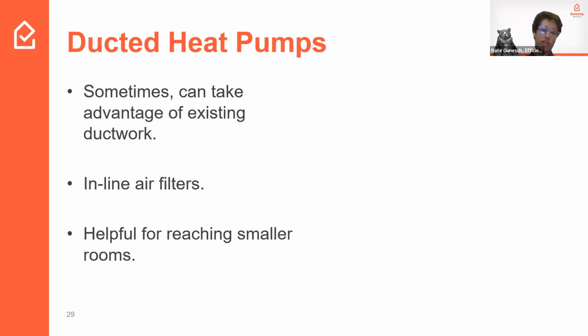The distribution temperature is kind of the key element for whether or not your existing ductwork will work. Sometimes because we've relied on the high heat from furnaces, people have installed leaky ductwork, or used building cavities as ductwork, and that's just not well suited for a heat pump. So that's a conversation to have with your contractor, but it's worth mentioning because it can really bring the cost down.